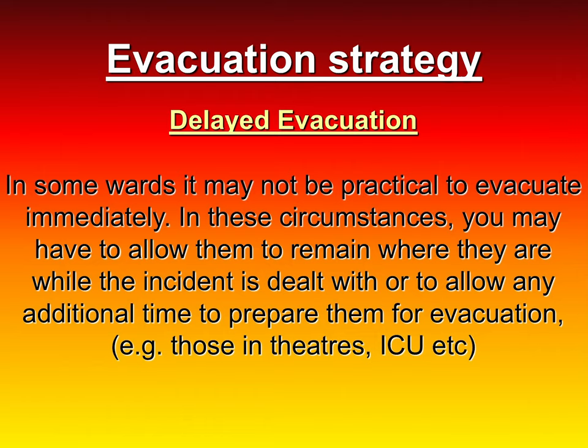Delayed evacuation may apply in some areas — for example, if surgeons are operating on a patient they can't just close down immediately. That situation has to be delayed. You'll find that in those areas the doors could be up to two hours' fire protection, but that protection only works if those doors are closed. Keeping those doors closed gives the surgeons time to close down the operation or complete it if they're nearly finished. Remember: if the fire alarm activates while a patient is in surgery, do not put anybody under anesthetic — don't put them to sleep until you find out what's going on.